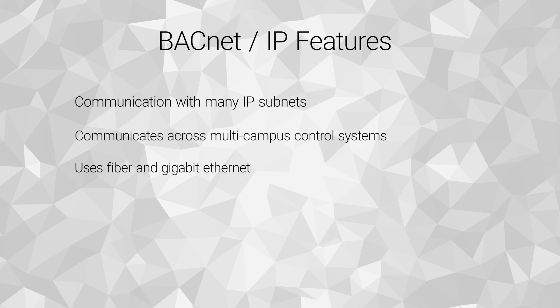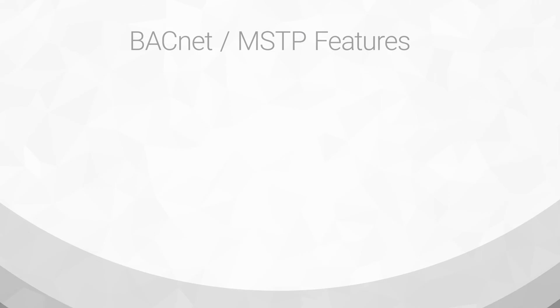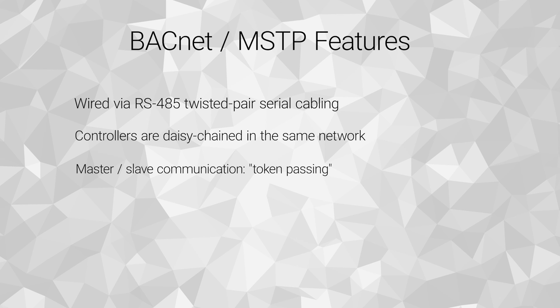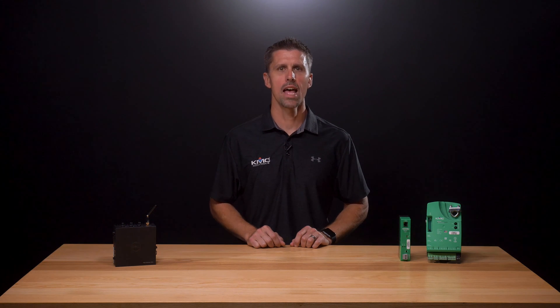BACnet over IP relies upon the protocol rules of IP and Ethernet. With BACnet over MSTP, each device is wired via RS-485 twisted pair serial cabling, daisy-chained together into one network. Communication is based around passing tokens, which is a way for devices on the same MSTP network to take turns initiating conversations with other devices. Only master-type devices can have the token and request or send data without being specifically requested. Sensors are sometimes manufactured to operate as slave devices and can only send messages when specifically requested — they never have the token. All KMC devices are masters and can talk on the network directly.